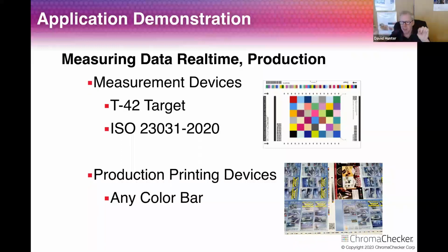And if the instrument has a real low straight line, then you can build an ISO report that meets the ISO 23031 spec to prove to the ISO 9000 committee that your instrument does not need to be sent back to the factory, and you get fully utilized time and effort with that instrument.